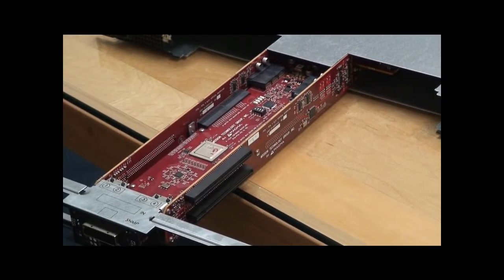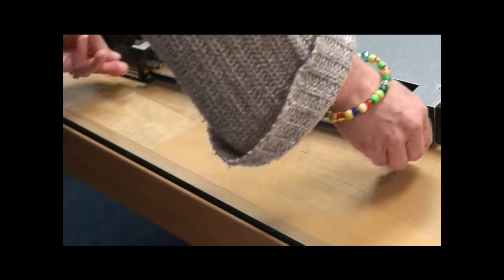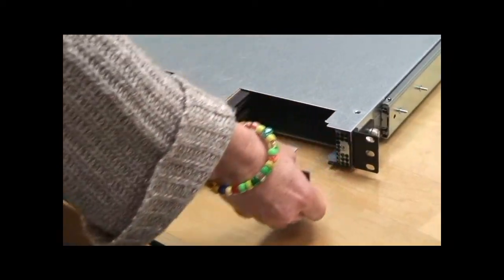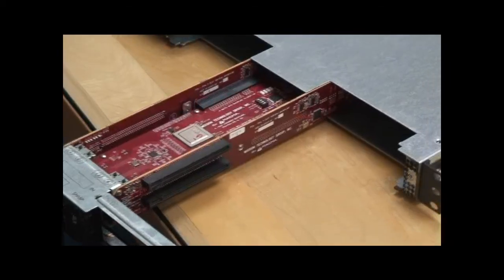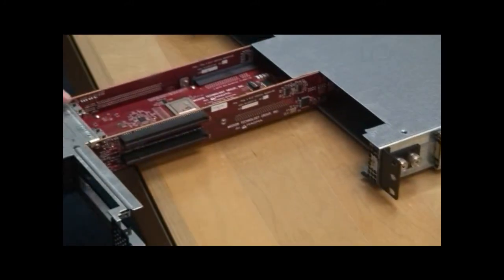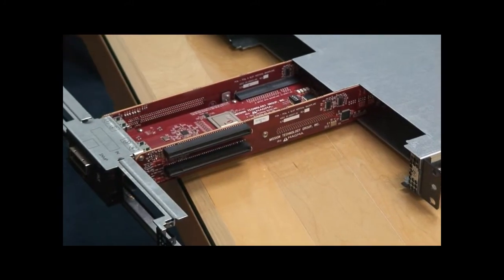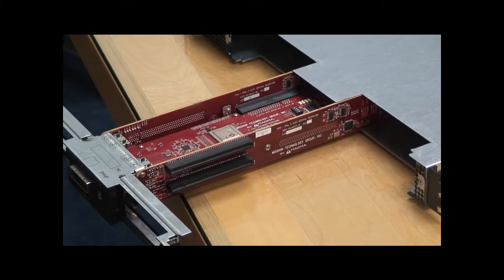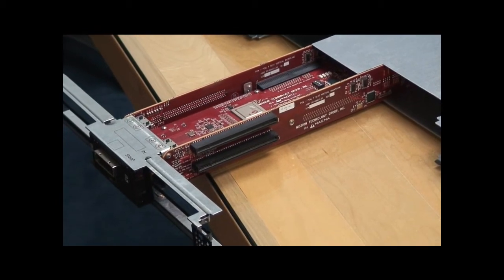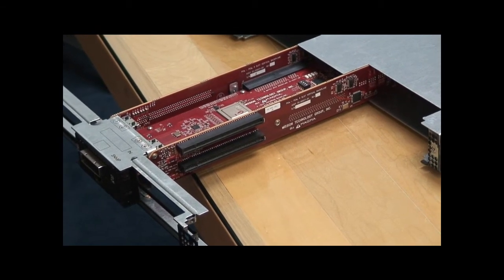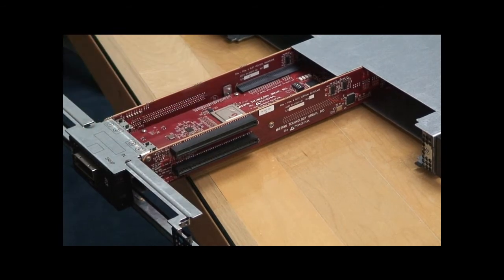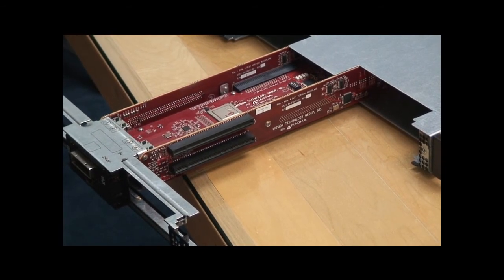You can take this card carrier in and out with cards in it and the chassis fully powered. The reason for this is to push a button, turn off power to the slot, take the card out, replace it with another card, without shutting down the chassis that may have other critical cards passing data at that time.